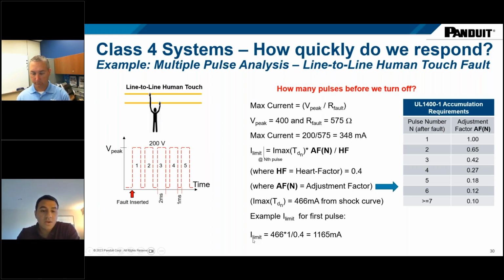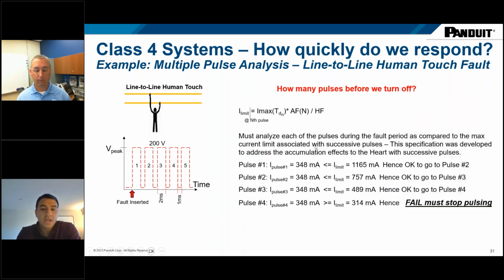So we go through a calculation. Right now we get to what's called the current limit, which is listed on the bottom here. And now we also have what's called the maximum current. This is based on this specific system. The maximum current is 348. And so we go through a calculation and figure out, I'm at 348, the limit is 1165. I'm good on the first pulse. I can go to the second pulse. You keep going down, you can see that the current limit keeps dropping until you get to a certain pulse, and then it basically says, this is too much and you need to turn off. So in this specific system, you can only pulse 3 times. The 4th time, the system must turn off.